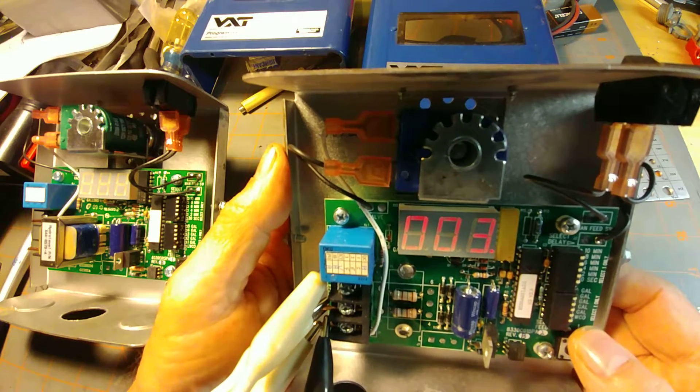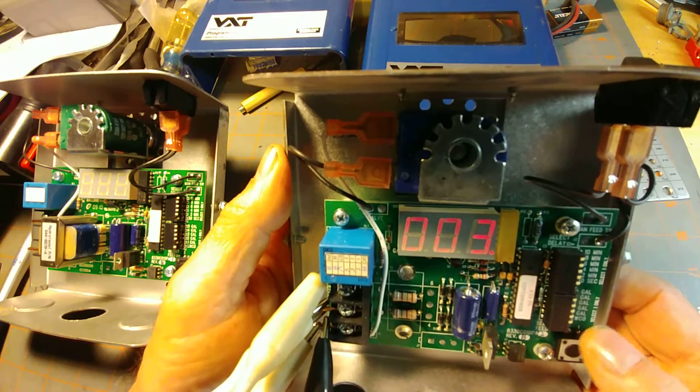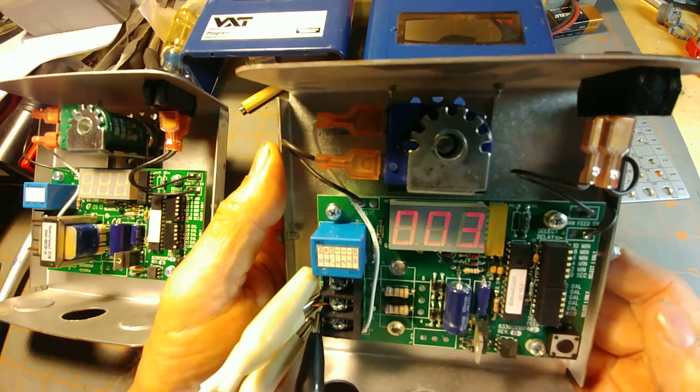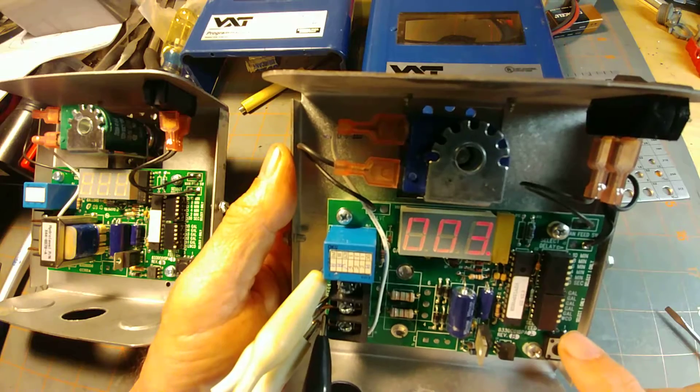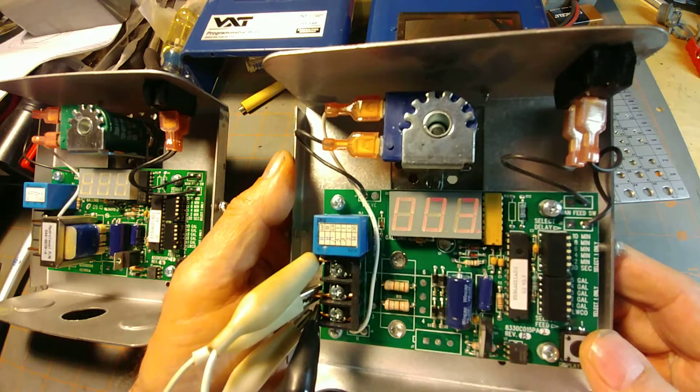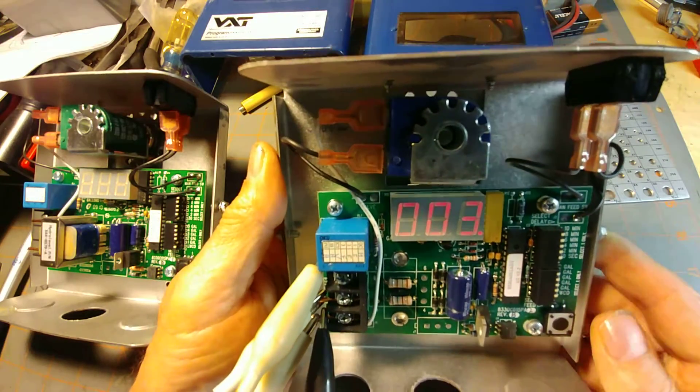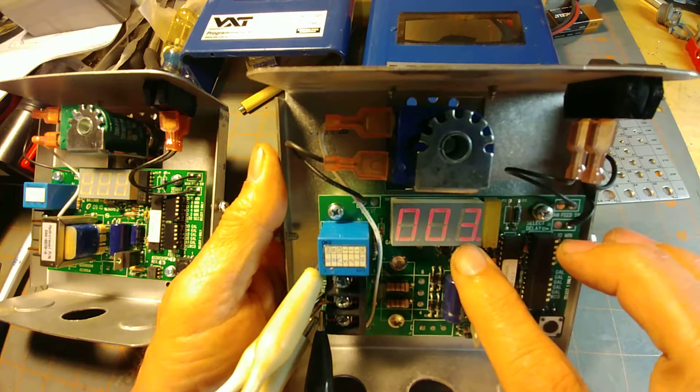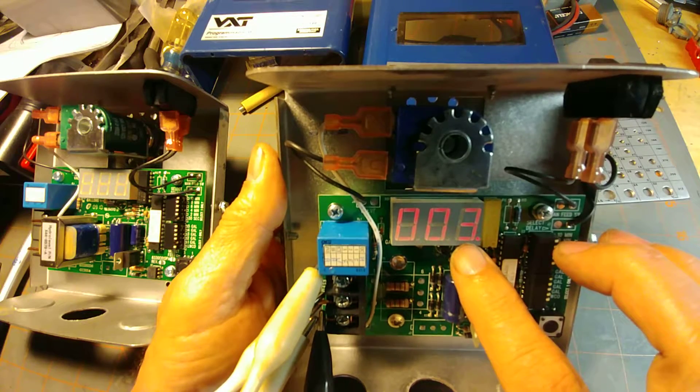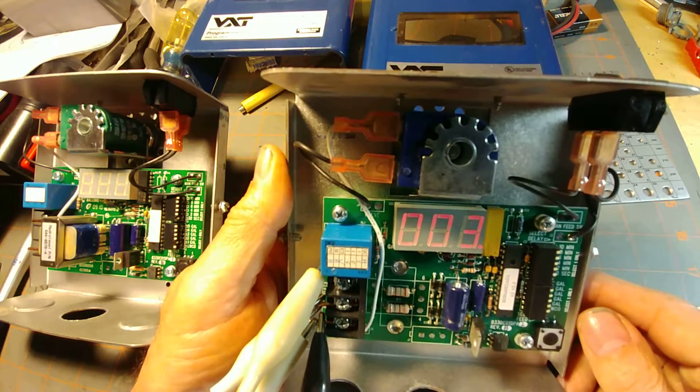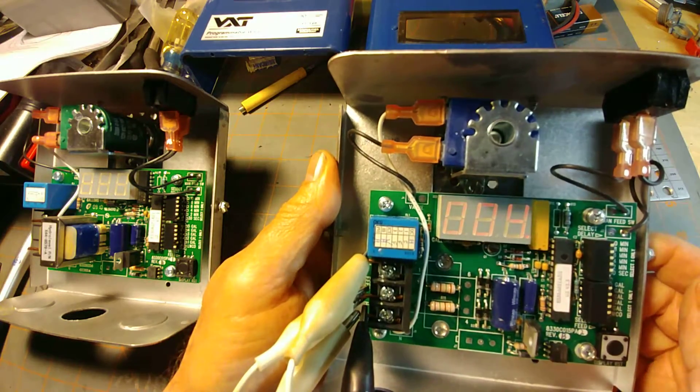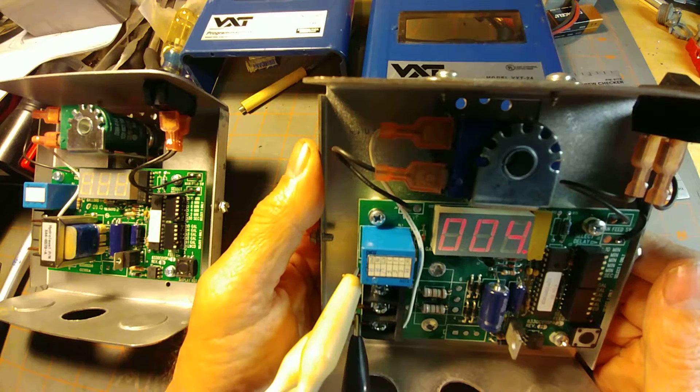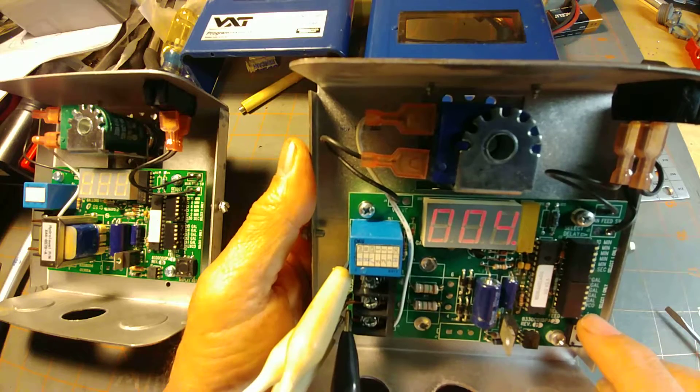What could be happening is now the boiler is filling and filling and filling. The low water cutoff is malfunctioning and continuing to call for water when in fact the boiler is now flooding and you've got water squirting out of radiator vents all over your building. As you can see, I don't remember we started at 2, we're now at 3, and it'll go to 4 and keep on feeding until we withdraw the signal. So this is not an advisable setting.